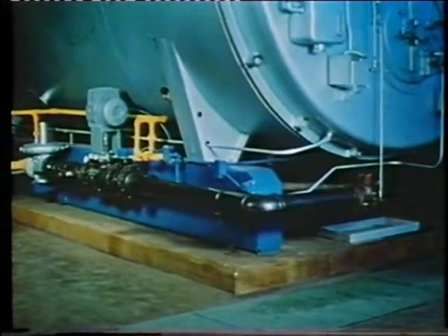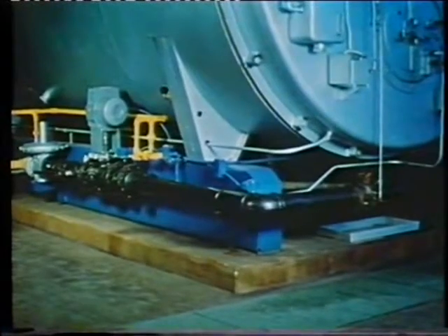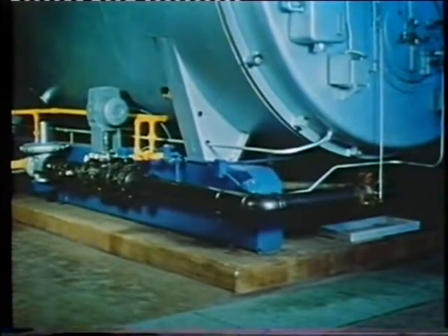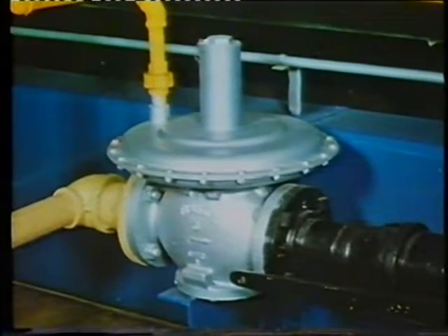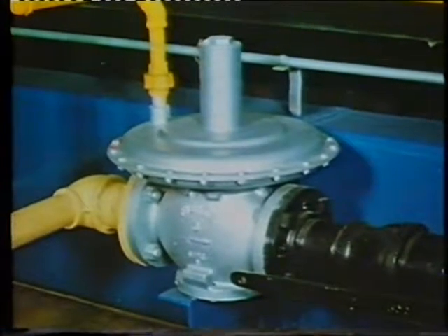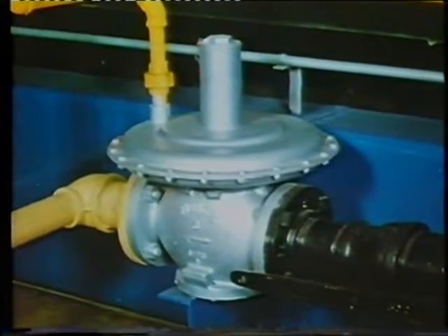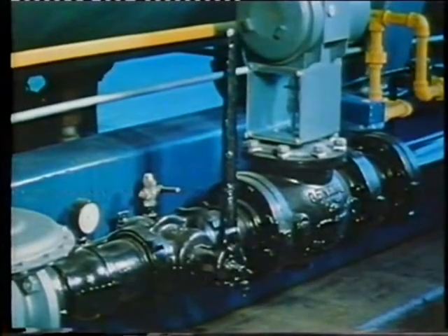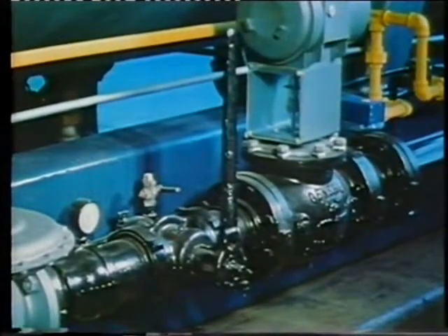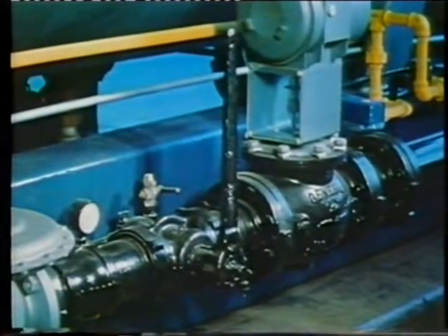A boiler gas fuel system is slightly different from the oil system just described. Gas for the pilot and main burner may be supplied at main line pressure. In a typical gas train, the first item in line is the pressure regulator, which reduces the line pressure to the pressure required at the burner. The manual gas valve provides a shutoff for the gas line to the main burner. The pilot gas train is tapped ahead of this main gas valve, so the pilot flame can be used for either fuel.